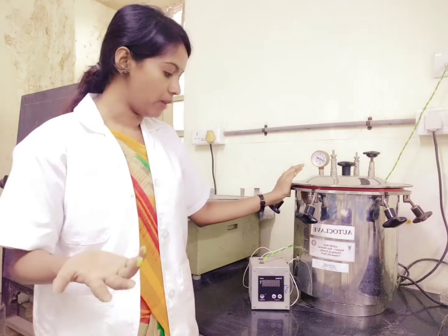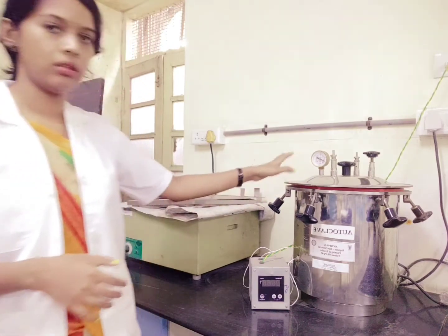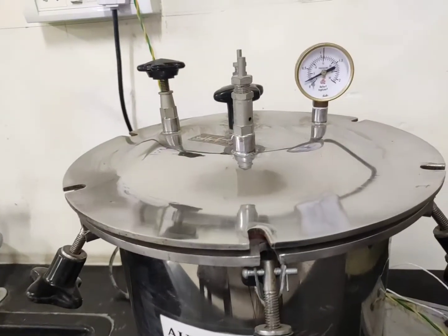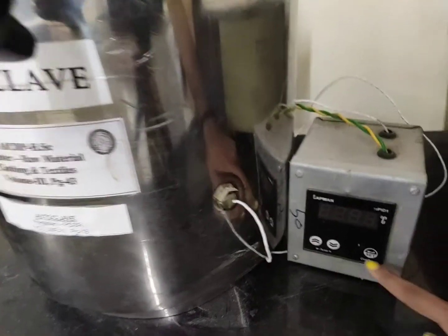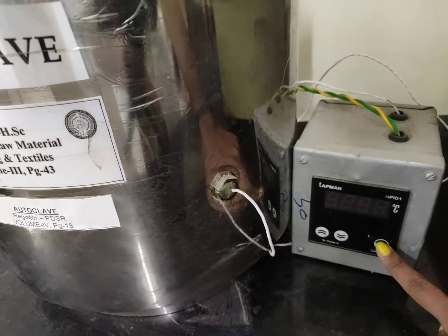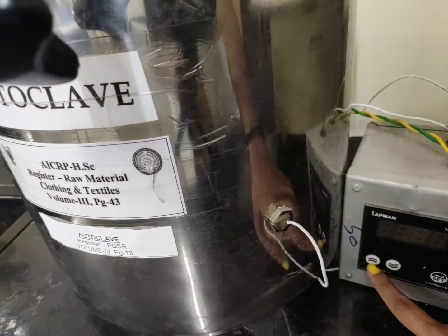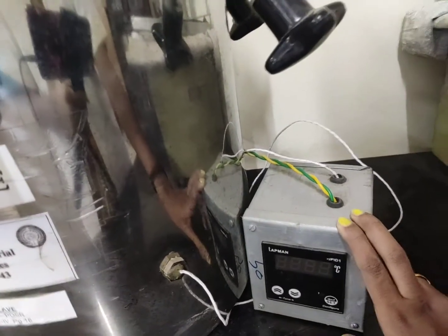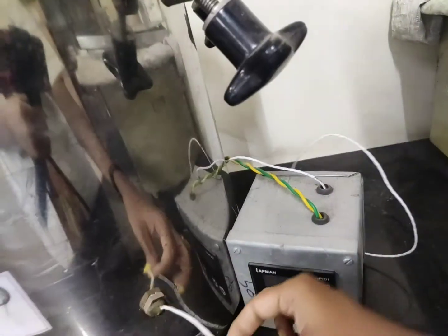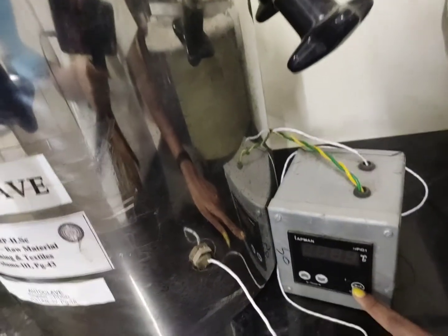Now I will let you have a very close look at this instrument, so that you can see the different valves that are present. You can see the instrument comes with this control panel, where by clicking on set, you can set the temperature that you want. For autoclaving, we will set 121 degrees centigrade. With this tuning, you can increase or decrease the temperature. It is also attached with a sensor. This white wire that you can see is attached to a sensor, which means this device can also sense the temperature inside. Once you have set the temperature you require and start the instrument, it will show the current temperature.